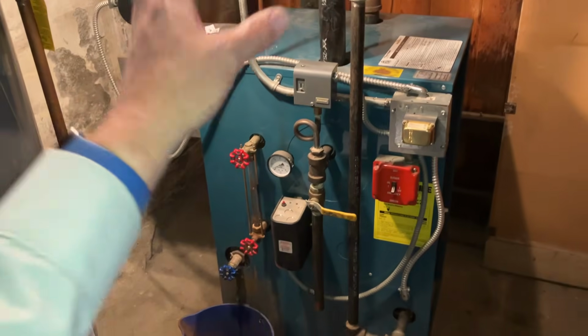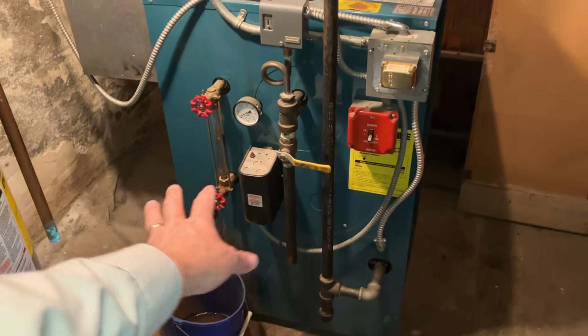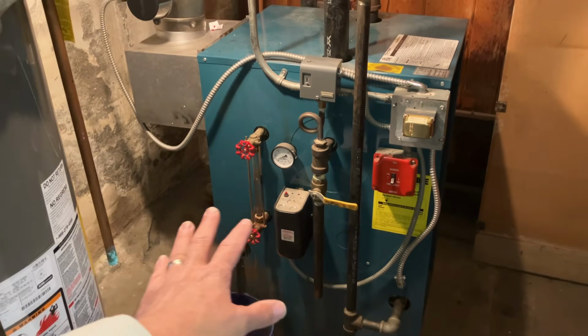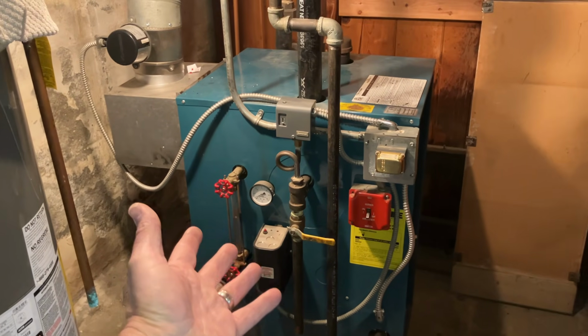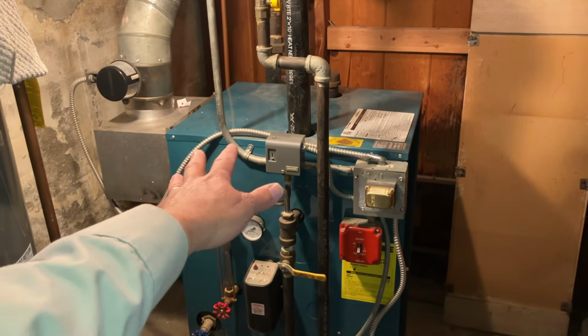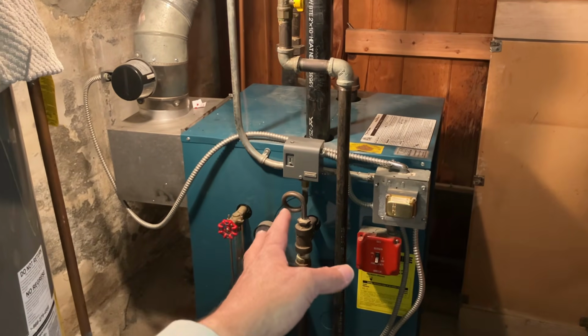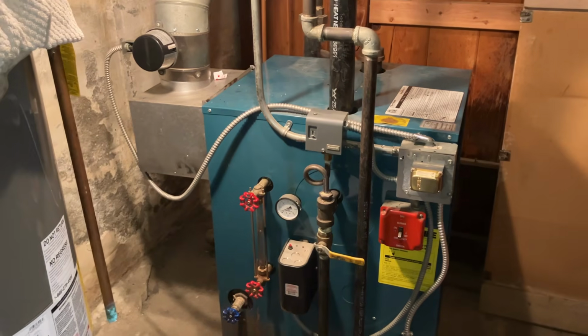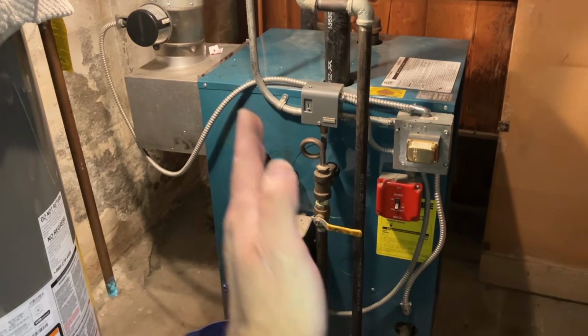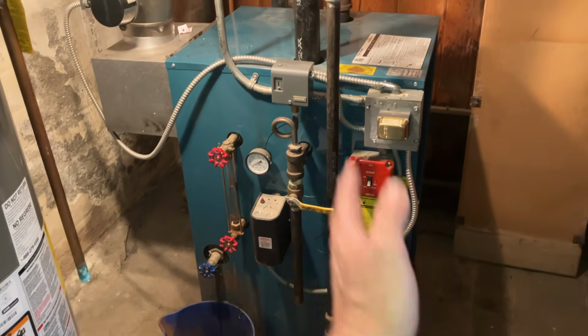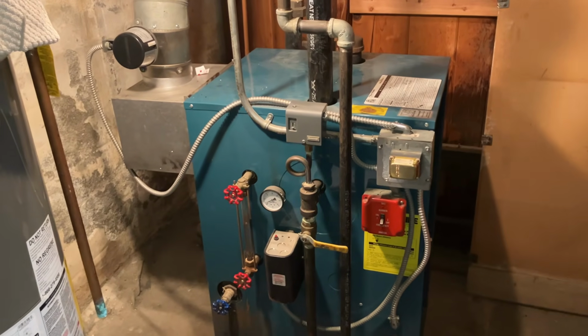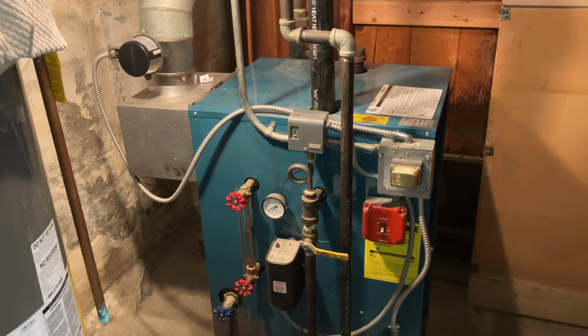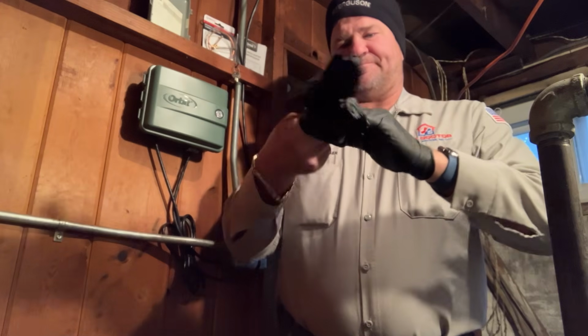And if you ever have any water dripping at the base of the boiler or inside the combustion chamber, you got a compromised heat exchanger, and you really need to replace the boiler at that point. Forget about scrubbing it, forget about cleaning the boiler, forget about taking it apart. You're gonna have to replace the boiler. We already filled up the boiler with water, no water leaking out of the heat exchanger, so we're gonna take this bad boy apart right now. Let's go. All right.